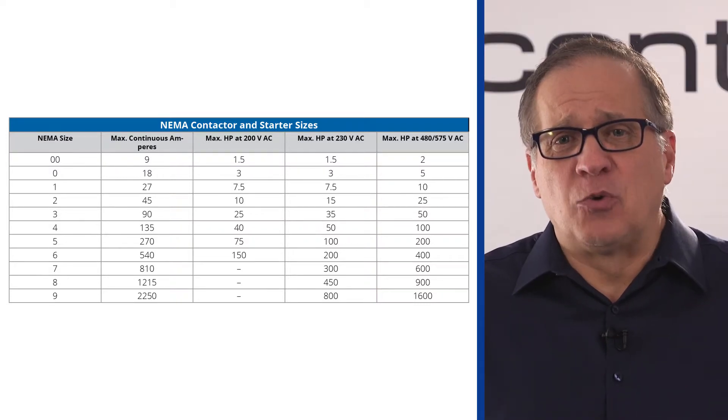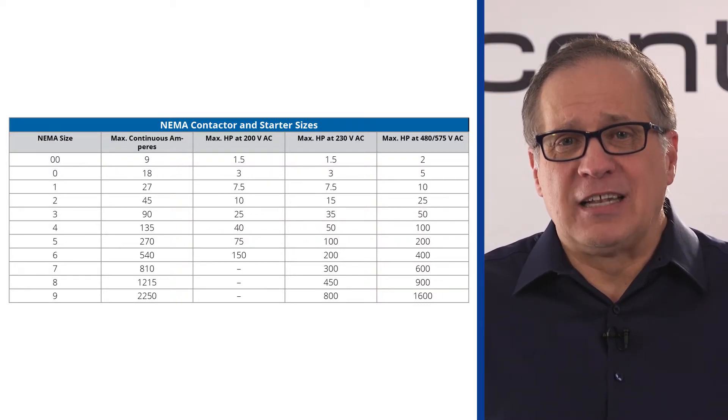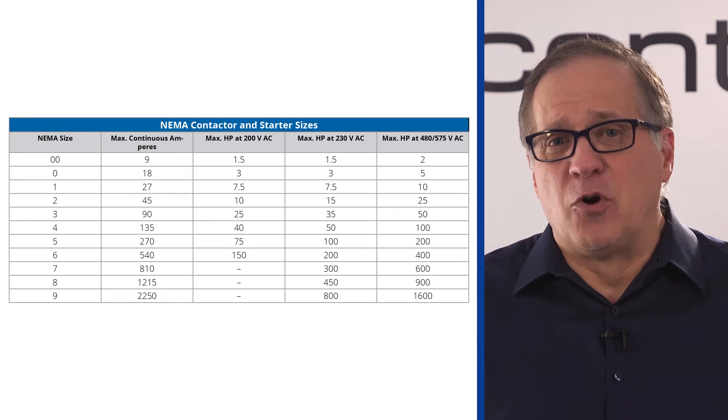It is necessary to know the voltage and horsepower rating of the motor when selecting the proper NEMA motor starter. In cases where there is a considerable amount of plugging and jogging involved, derating a NEMA rated device will be required.